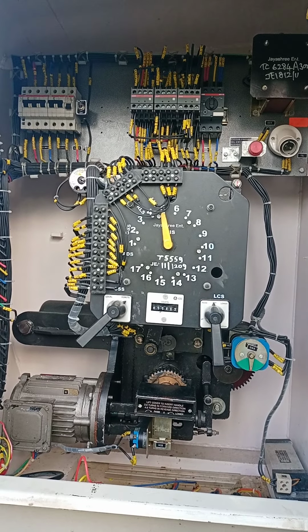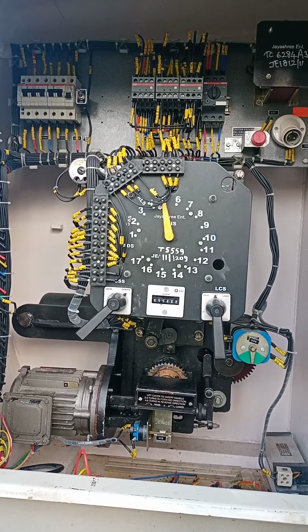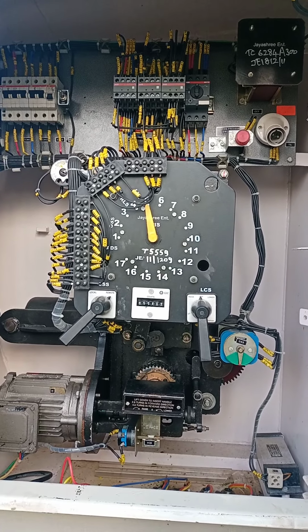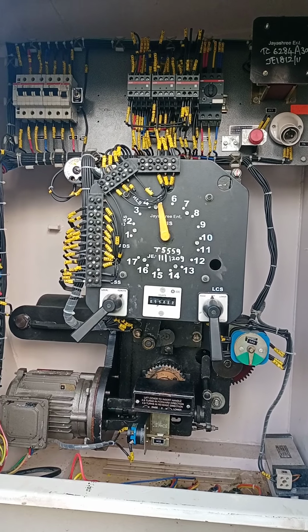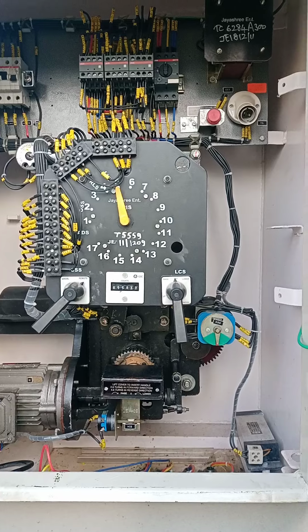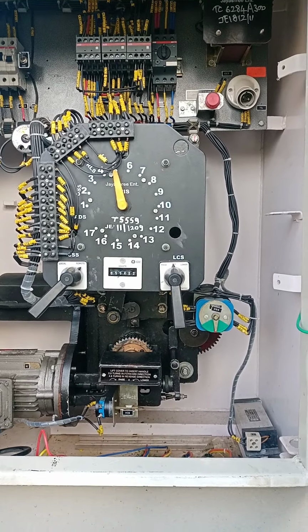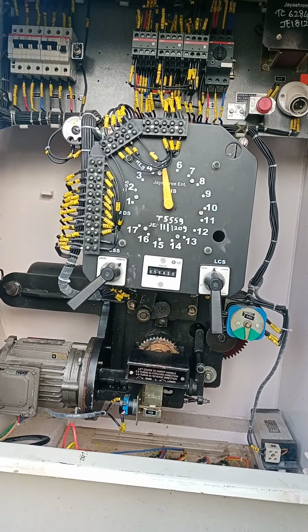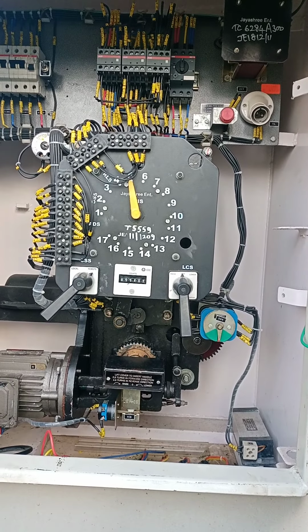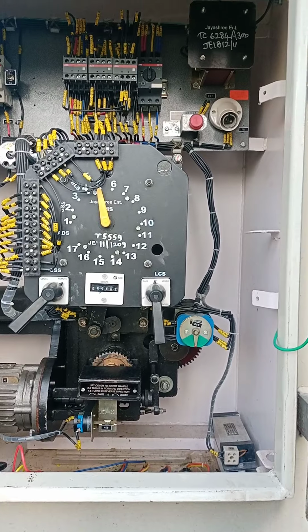For that we need on-load tap changers, that is OLTC, which is connected on the primary side for two reasons. One is that the primary side is on the high voltage, so the current it will take is less. The second reason is that your primary side is always in the external part, so the tapping can be taken easily. Now we will know about the operation of the OLTC.